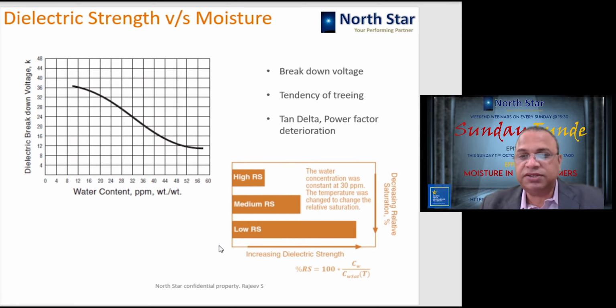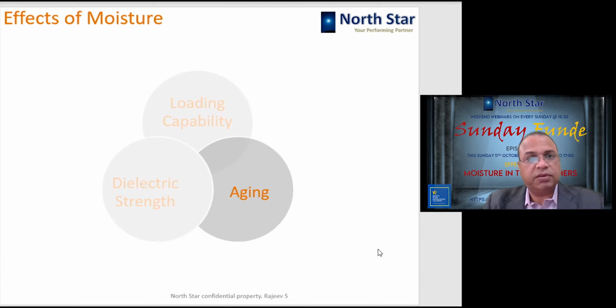So when this experiment is done, it was found that when the relative saturation is high, the dielectric strength of the system was low, and when the relative saturation was lowered, the dielectric strength kept on increasing. Okay, so very interesting finding and very useful to understand how the transformer relative saturation is an important criterion to judge the condition of the insulation. So this is how the dielectric strength of the transformer gets affected because of the moisture.